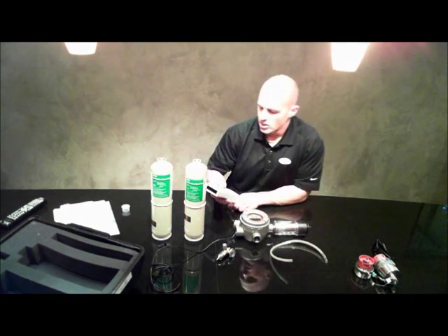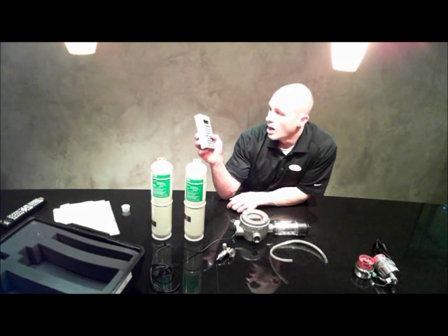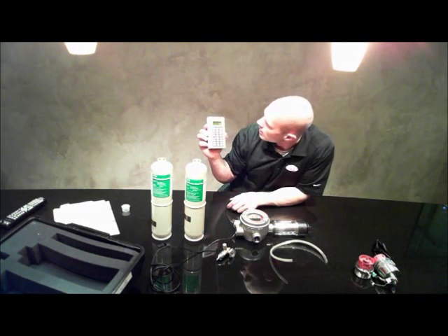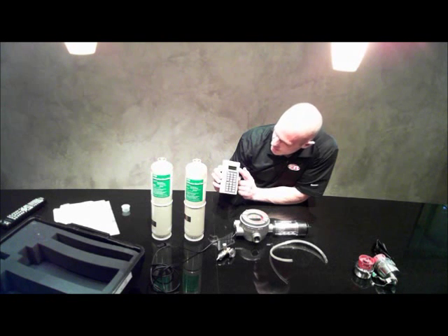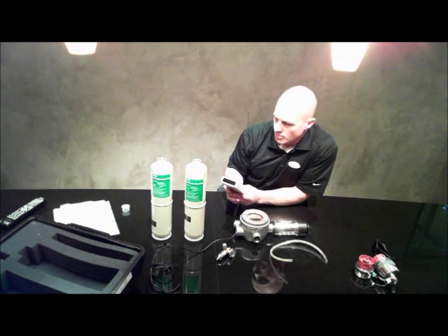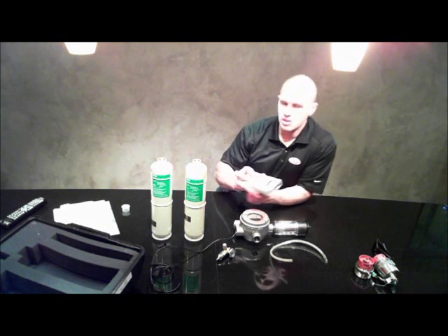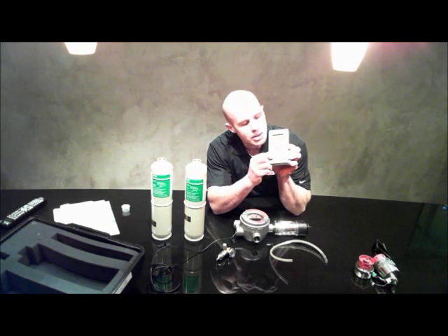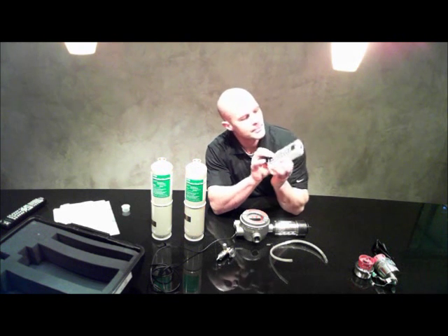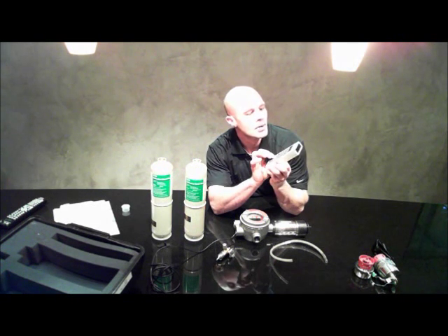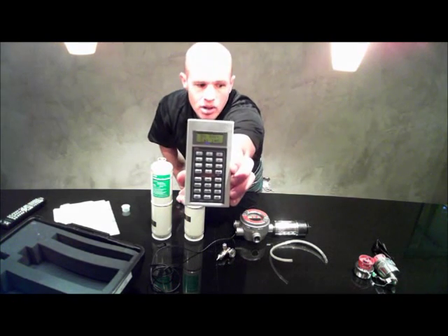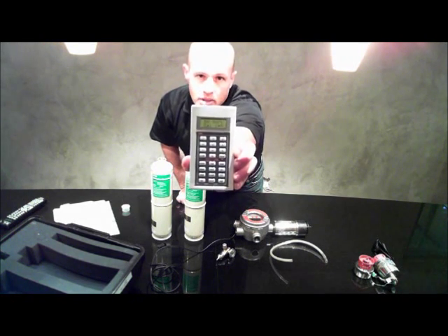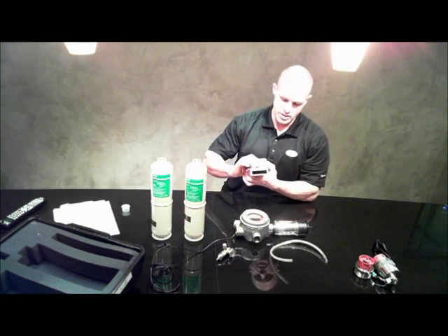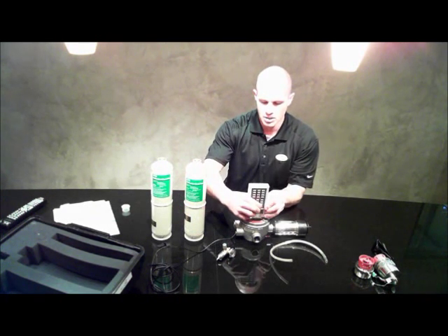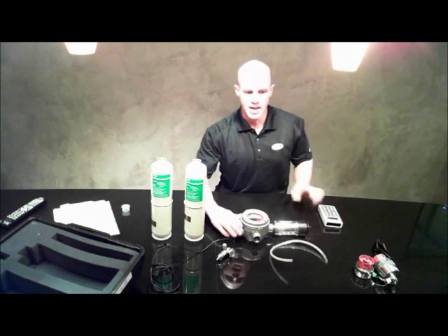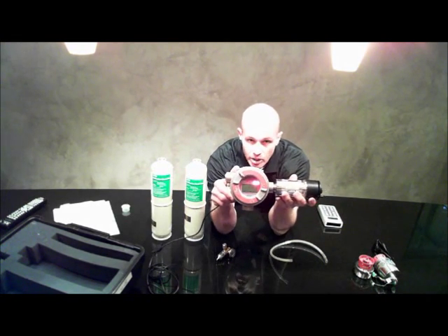So for an initial calibration on the MSA controller, I press enter to turn it on. It'll show the current version on there and then say ready. So what I'm going to do for an initial calibration is press and hold the span button. And that will say do initial iCal. Might be a little tough to see. I'm going to hold it over the monitor and press 1. And that puts this into a calibration mode.